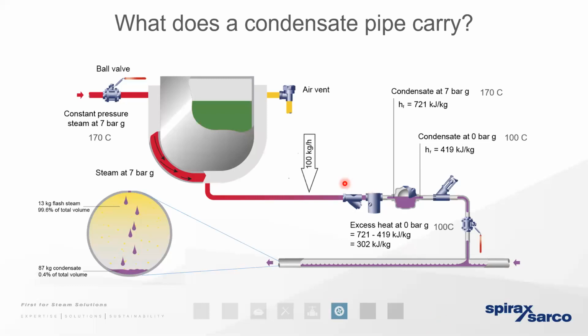At this point here, the condensate's under pressure. It's the same pressure as the process. At 7 bar gauge, the sensible heat in the condensate is 721 kilojoules. Now there needs to be a fall in pressure downstream of the steam trap, otherwise the condensate wouldn't move. And in the example of a fall in pressure to 0 bar gauge, well, the steam tables tell us that at 0 bar gauge, the condensate can now only hold 419 kilojoules of energy.